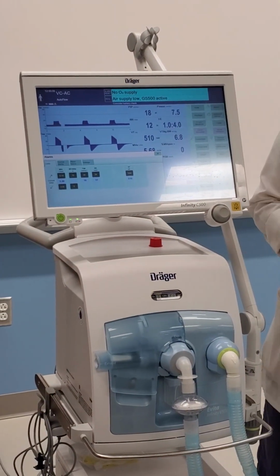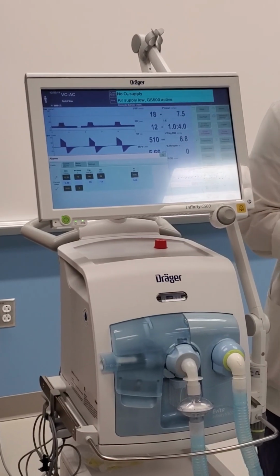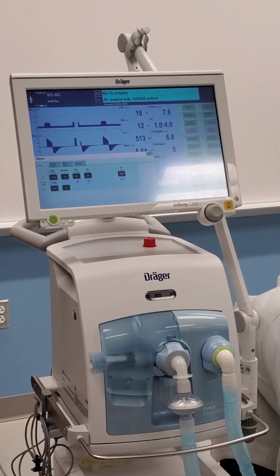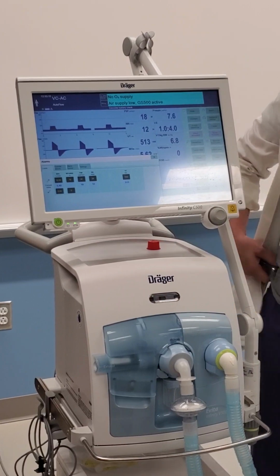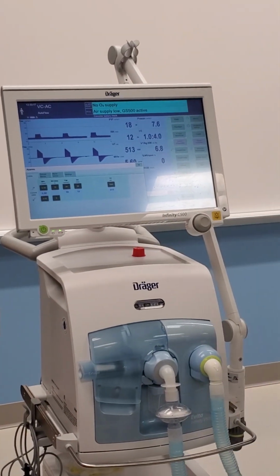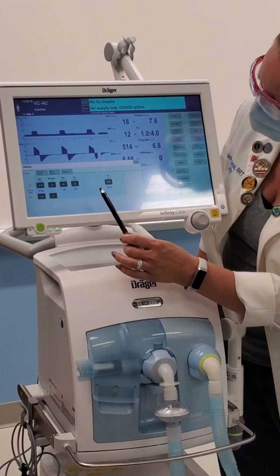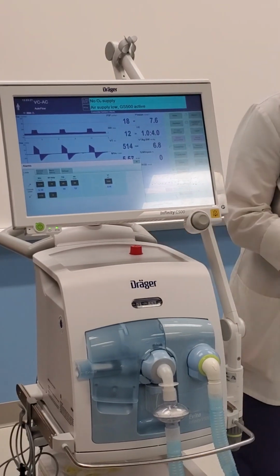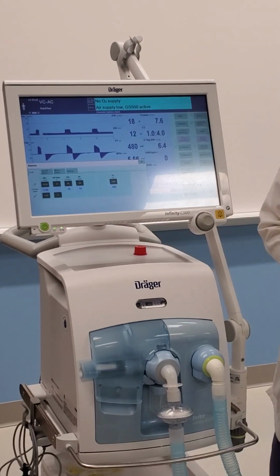What about in pressure control? How do we set our high pressure alarm? 5 above. 5 above your... It's the afternoon. You're all woke. You got up and had your coffee. 5 above your set PIP, okay? You have a respiratory rate alarm, which is 3 times, or 10 to 15 above.